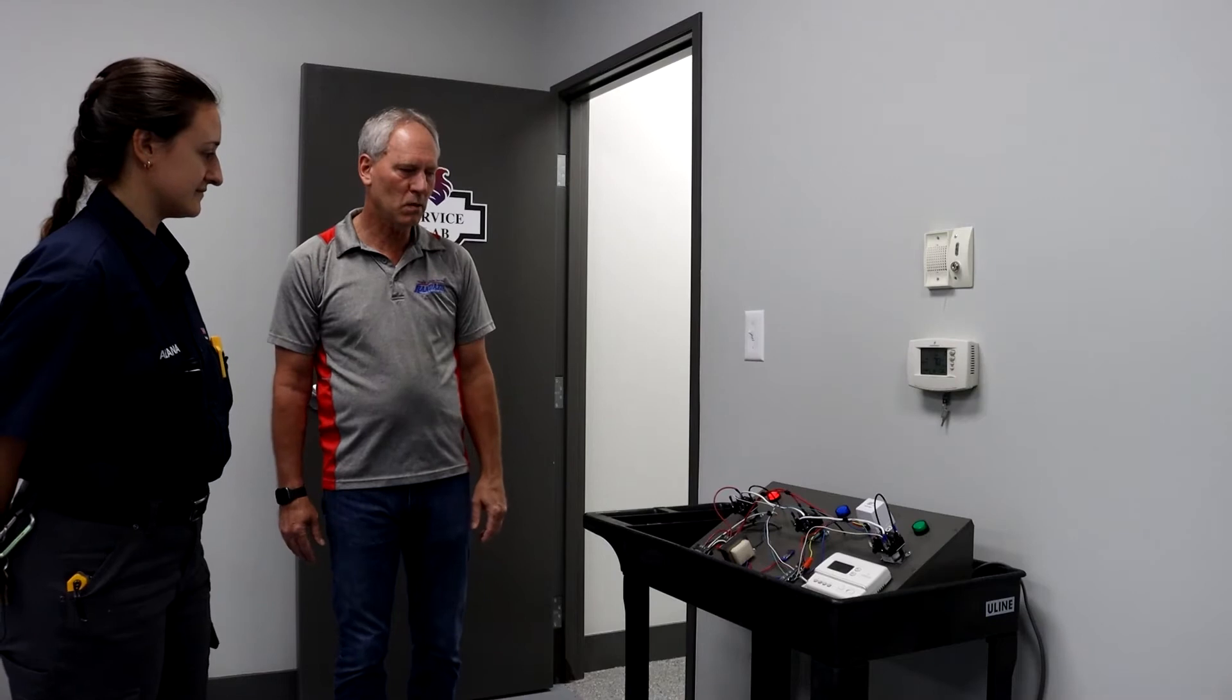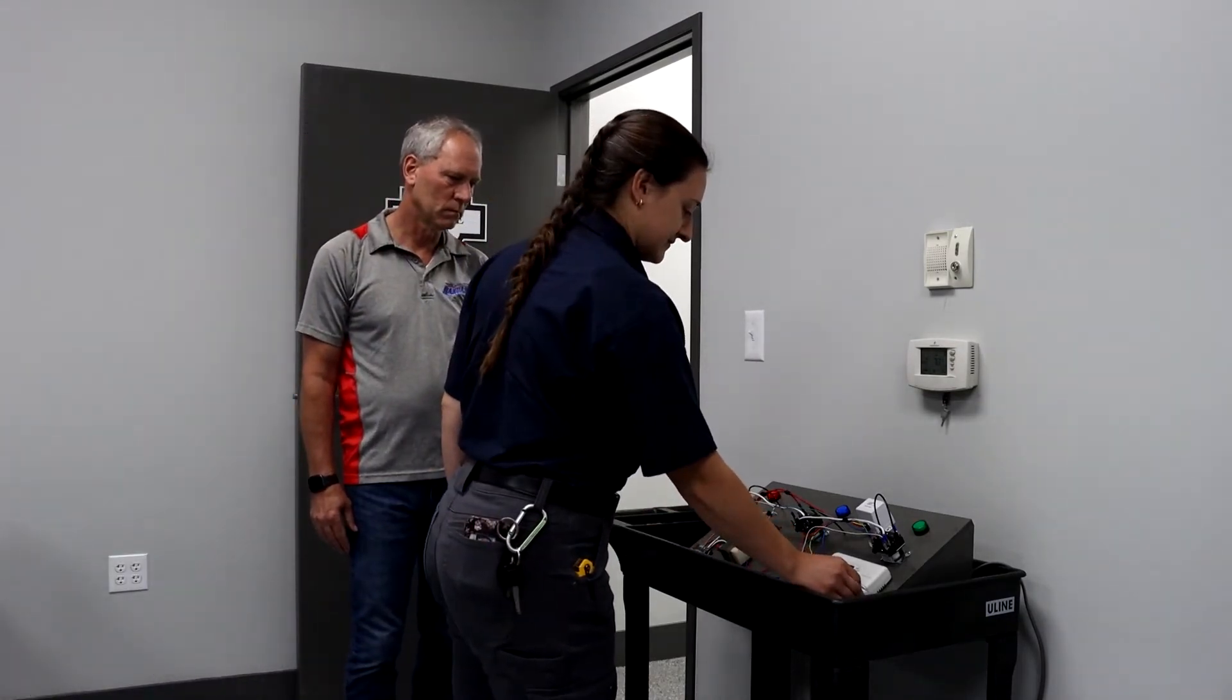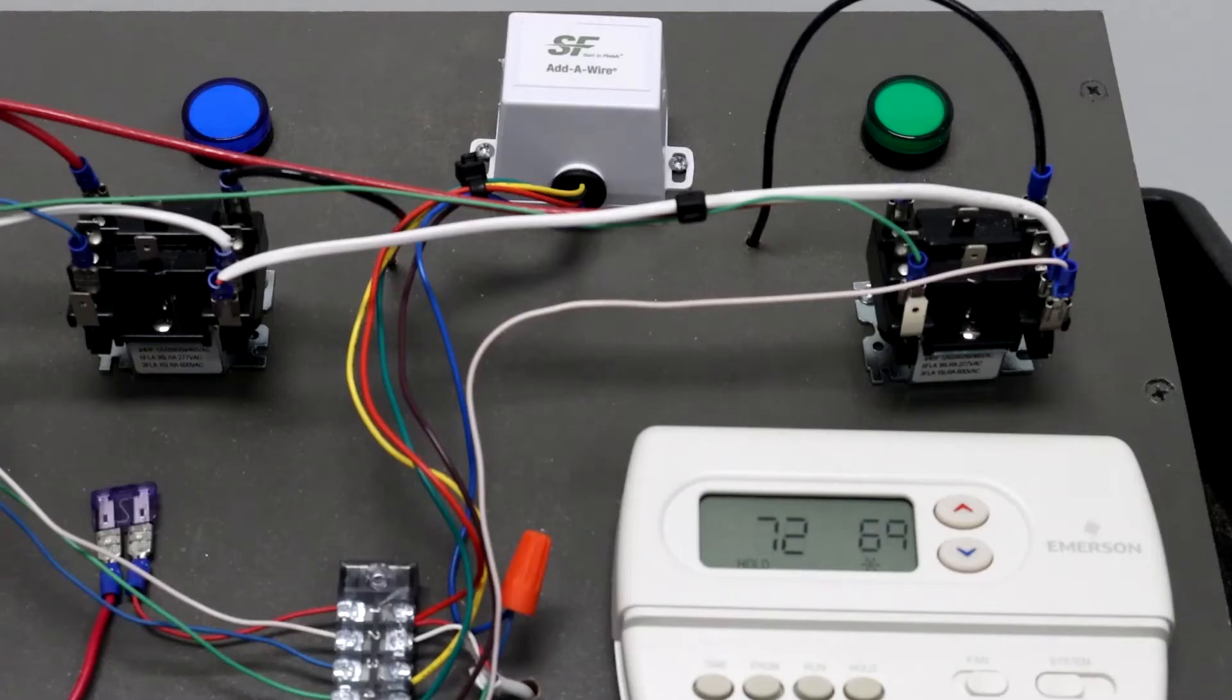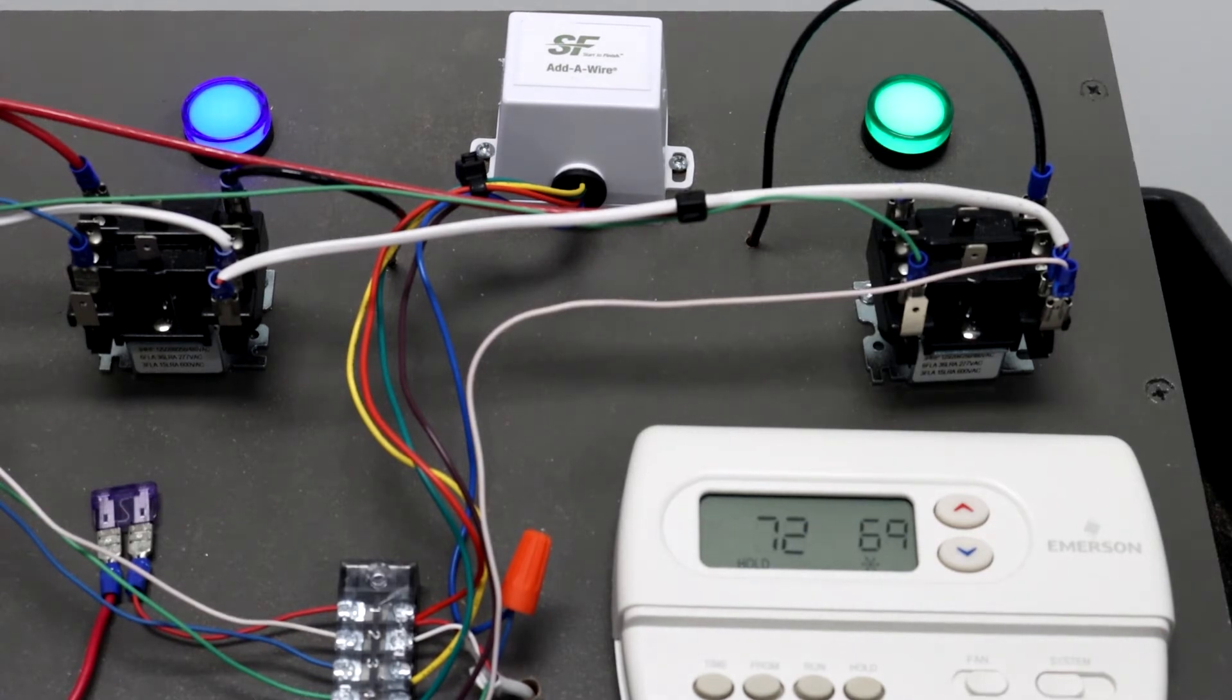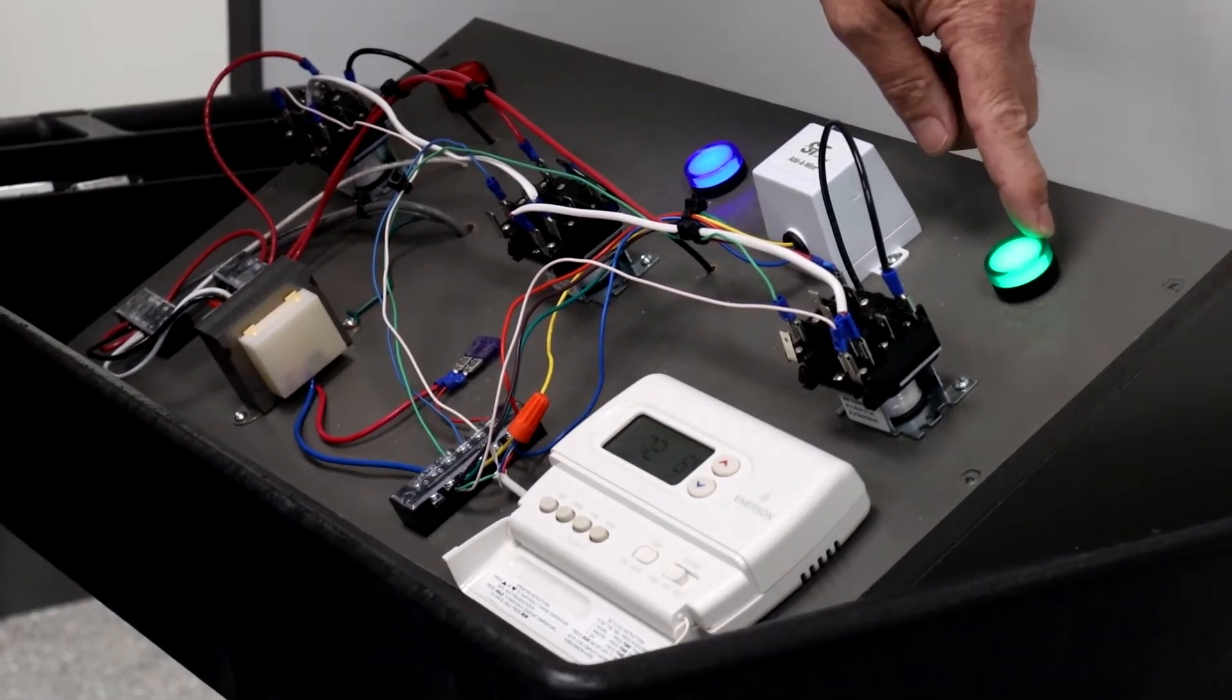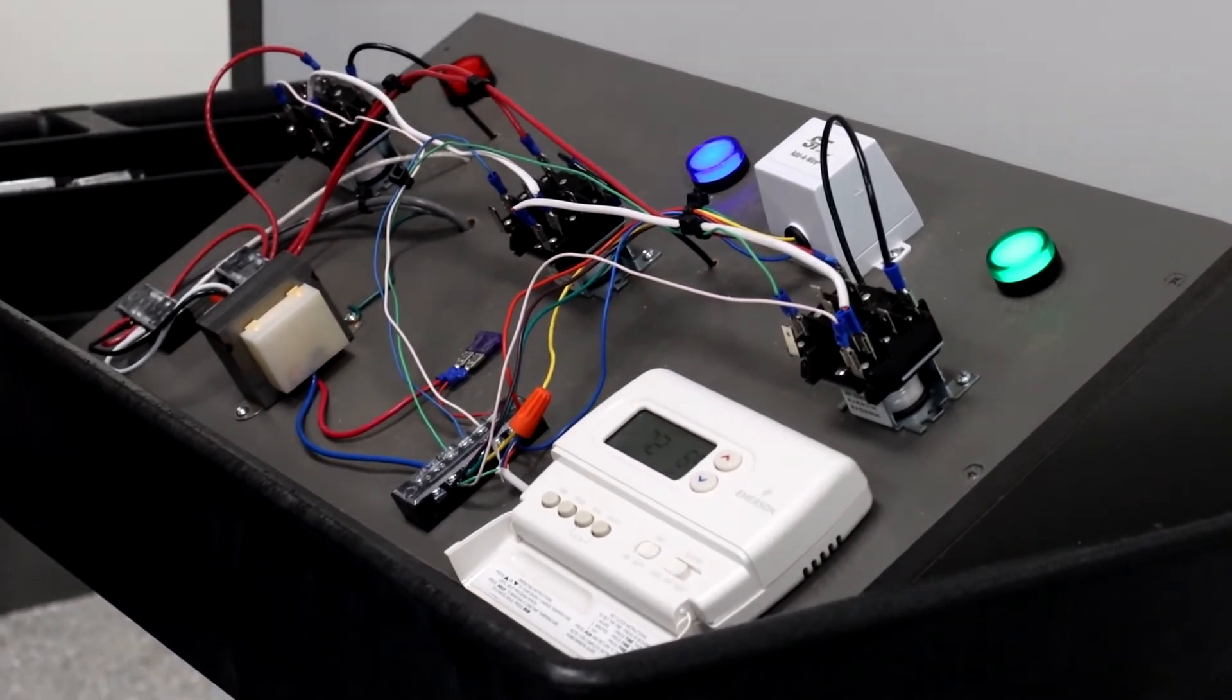Now let's switch it over to cool. At this point the thermostat's calling for cooling. It sends power to the blower relay and it also sends power to the contactor coil outside. The green light indicates the blower. The blue light indicates the relay for the contactor coil outside.